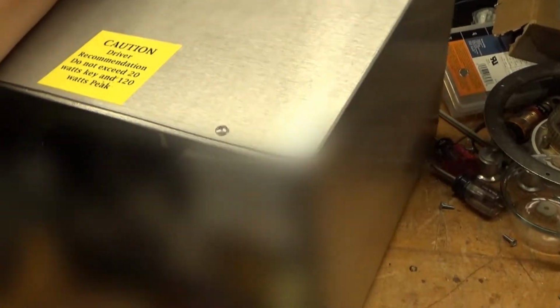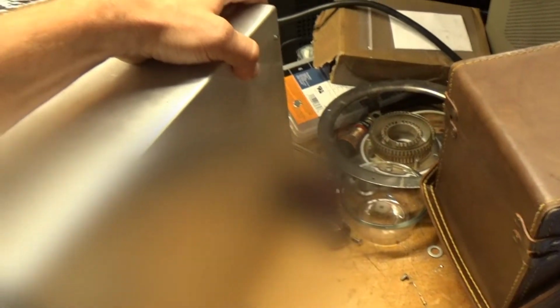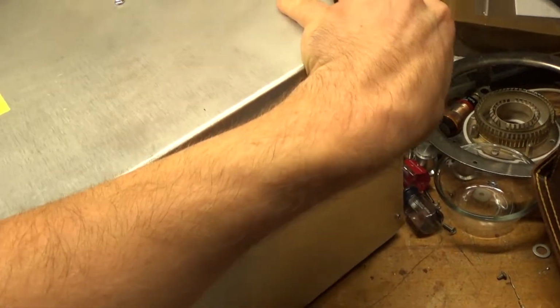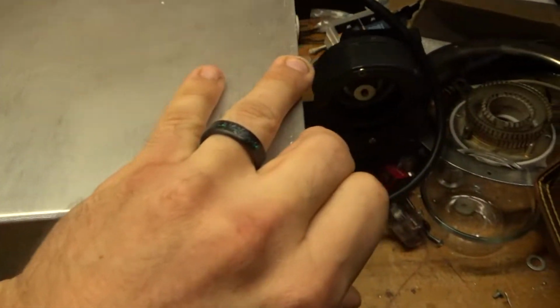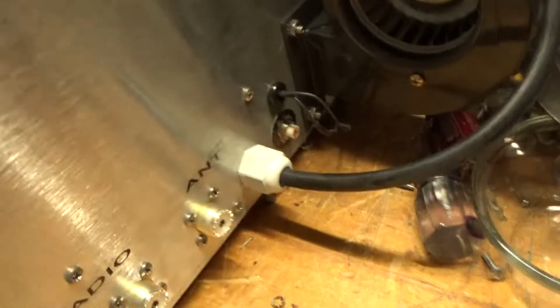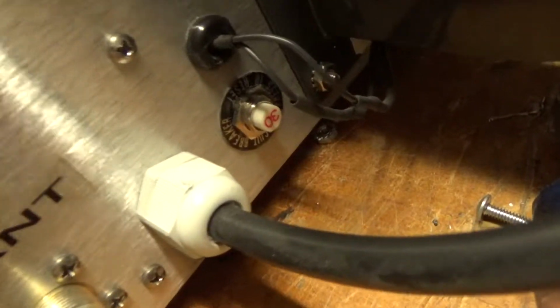I noticed it has a 30 amp breaker on the back. This unit operates off 120, so that's one thing that will have to be changed. That's way too big, as you can see. 30 amp.